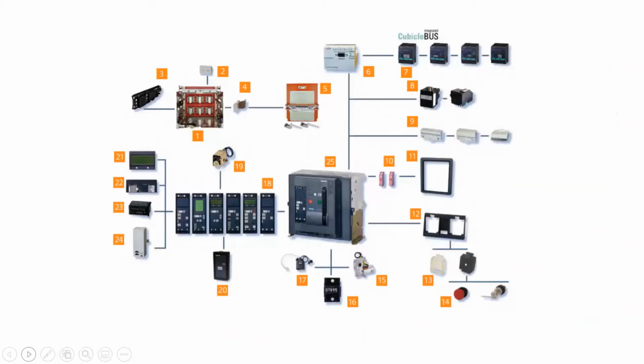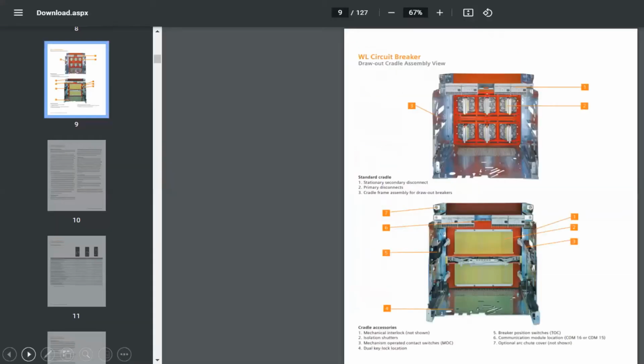Okay, go ahead. So this is cool. When you get in your manual, they show your flow chart of all your parts, right? So this is the inside of a cubicle. And how many people here have those rack in, rack out breakers? Good. I like the bolt in, right? The rack in, rack out are nice, because you can just turn the handle and the breaker comes out and you can maintain it and check it. Don't rack it out when it's live. And don't rack it in when it's, they say you can. And you see these little yellow, those are little windows. And when you rack it out, the little windows close and they're going to keep you from touching the live parts on the bus bar.